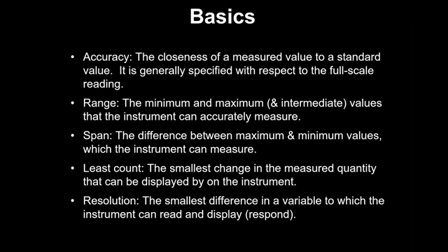That is the least count. If you take an RTD based instrument, which is normally used for chilled water readings, it could have a 0.1 least count. There are instruments which could have a 0.01 least count. So the least count will give you the extent of reading you can get, and that also indirectly reflects on your accuracy and the quality of the reading.